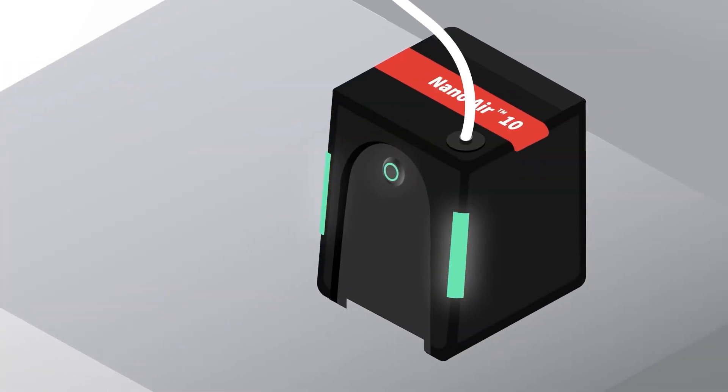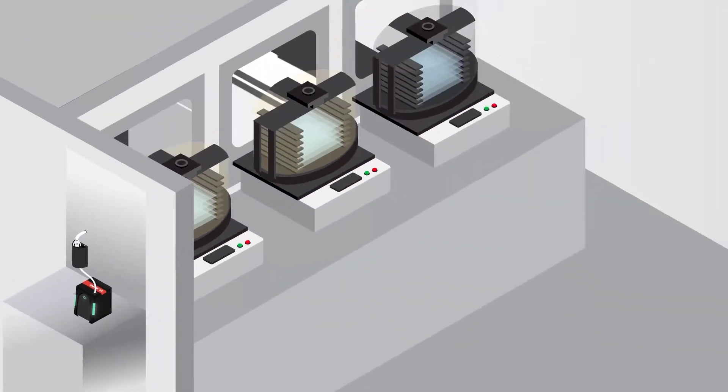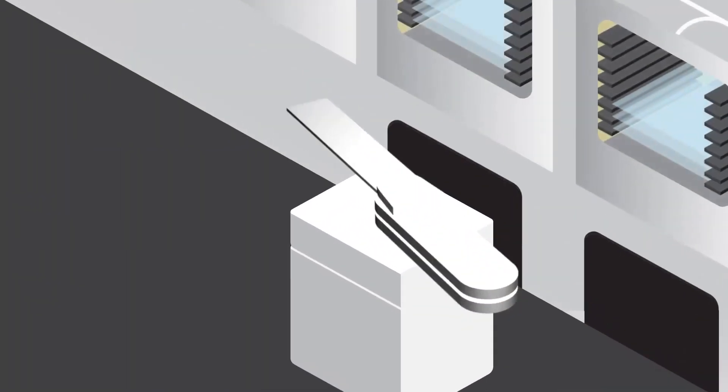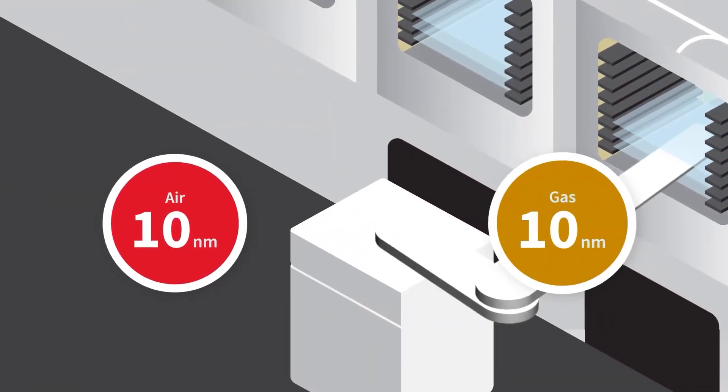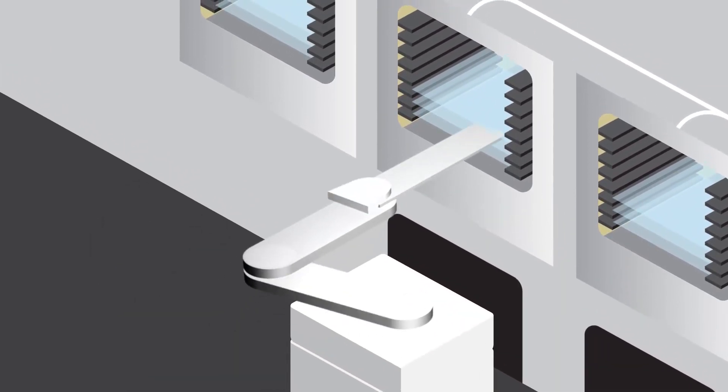Our newest industry-leading sensitivity aerosol monitor for critical fab and on-tool spaces is the NanoAir particle counter which effectively counts particles down to 10 nanometers for air and gas providing continuous actionable data for quick response.